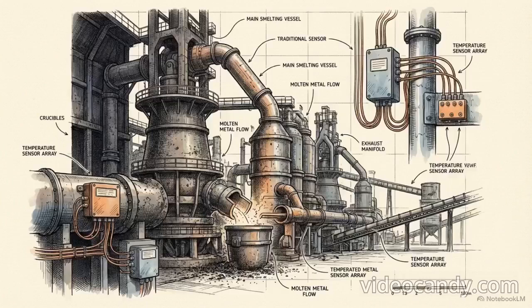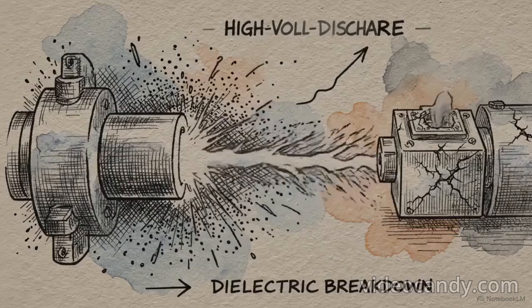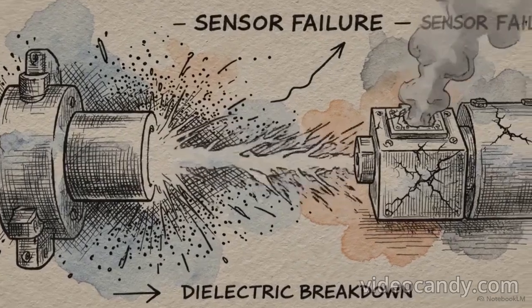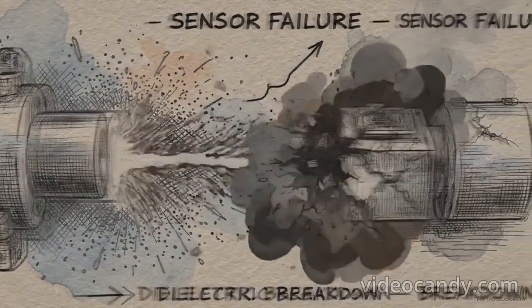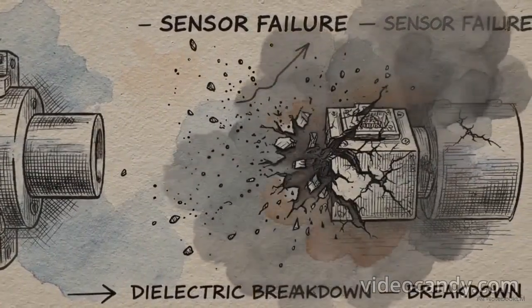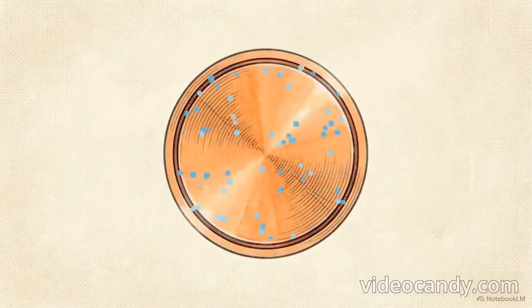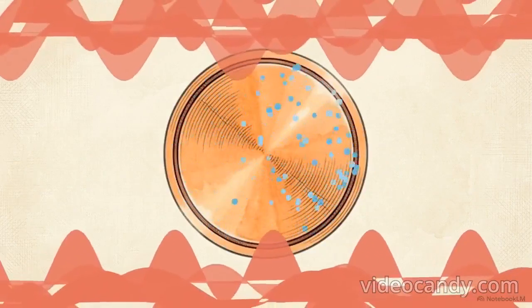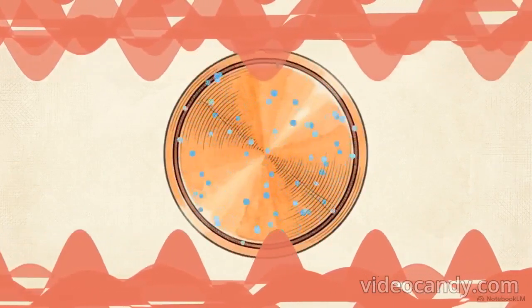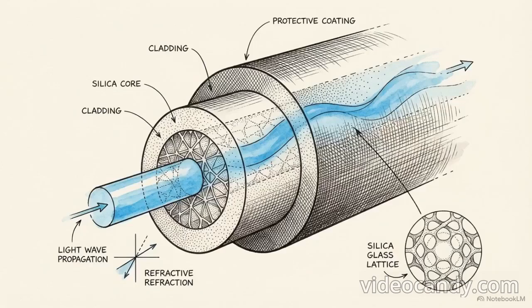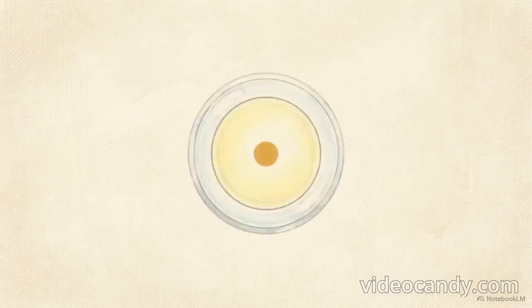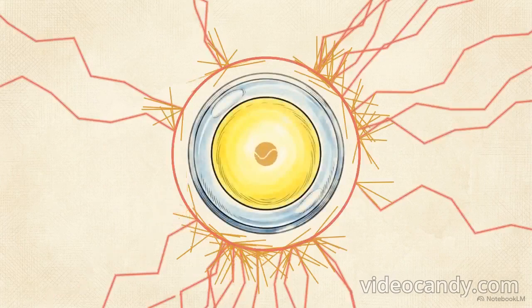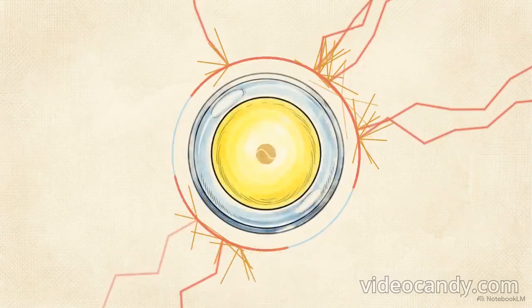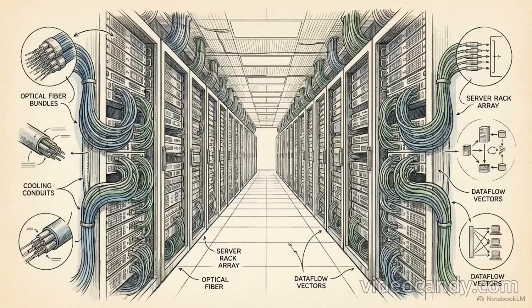To measure extreme industrial environments, engineers have traditionally relied on electronic sensors, but deploying these sensitive devices near high voltage or heavy electromagnetic interference introduces a severe risk of catastrophic failure. The flaw is inherent to the architecture. Traditional instrumentation relies on the flow of electrons, which makes the sensors themselves highly vulnerable to external magnetic and electrical fields corrupting the signal. The structural solution to this interference is optical fiber. Because the fiber is composed of inert dielectric materials, specifically glass, it is completely immune to ambient electromagnetic interference.